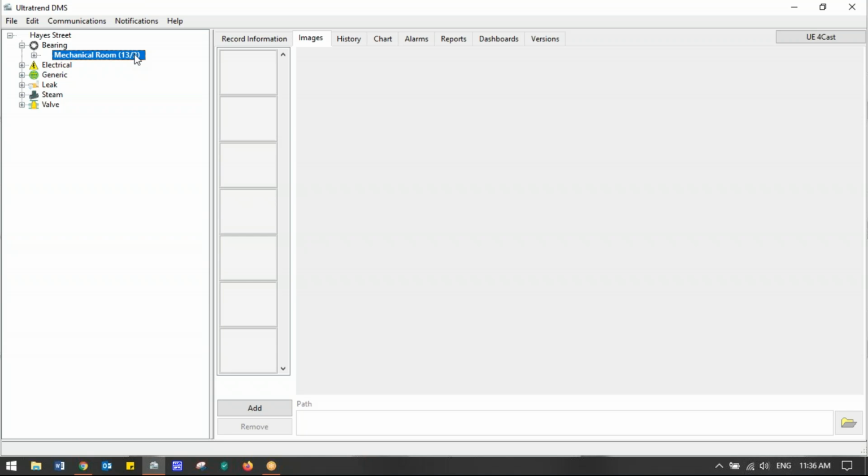And then to the right shows you how we split up the names of the 16 characters to use the location or machine and the actual test point. So this route was built using a 13-and-3 split. So motor 1, INB, inboard bearing. So motor 1 would be the machine or location, INB would be the test point. So I hit the plus sign on that, and we have one machine under here, motor 1.